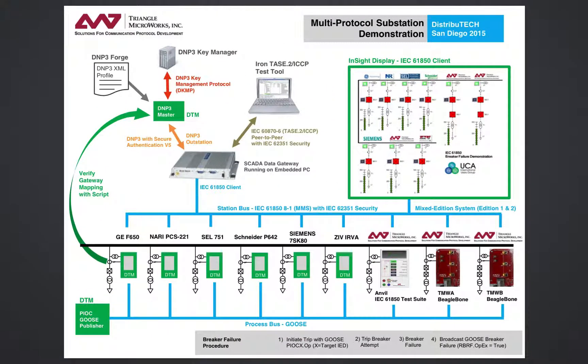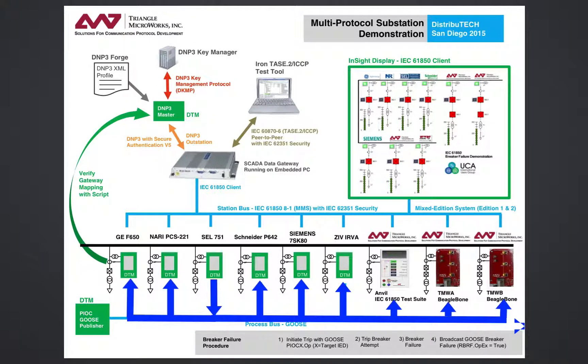For the breaker failure simulation portion of the demo, a trip can be initiated remotely using a GoosePIOC.op message. The breaker attempts to trip and simulates a breaker failure. It then broadcasts a GooseBreakerFailureMessage or RBRF.opEx equals true. Upon receipt of this GooseBreakerFailureMessage, each of the other devices will trip their breaker.